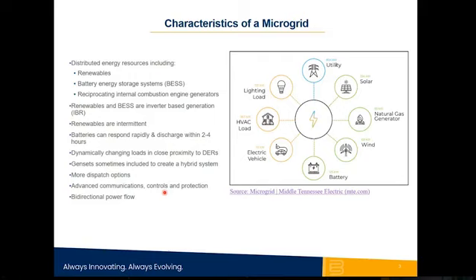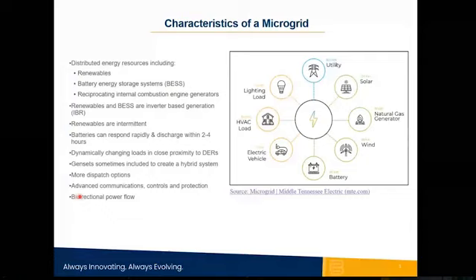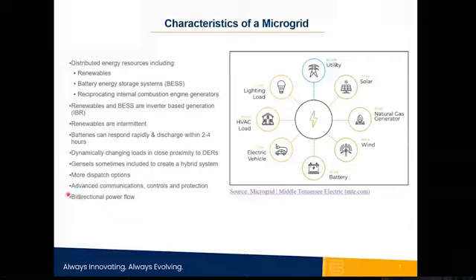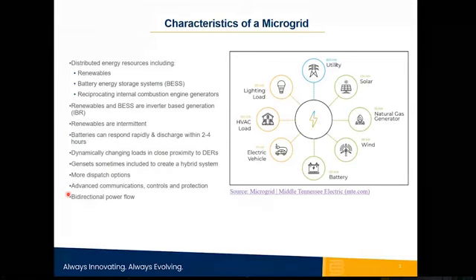And the other thing is bidirectional power flow, because traditionally you would have a power plant that would output power radially to the loads. But today, with distributed resources at the grid edge, you have power coming from all different directions. And because of this bidirectional power flow, protection algorithms need to be updated to accommodate that.